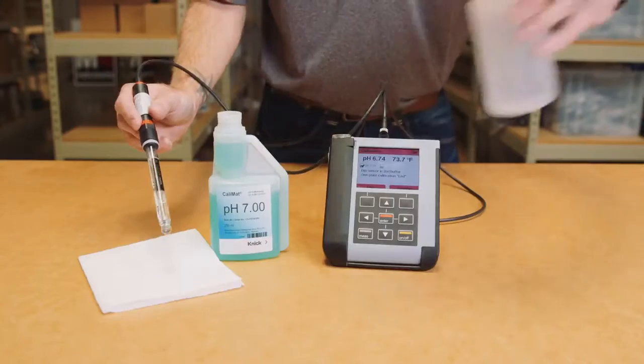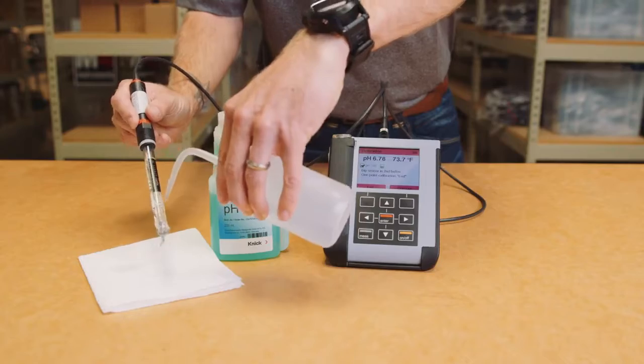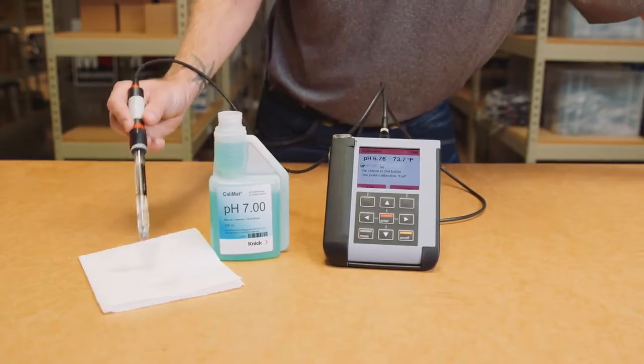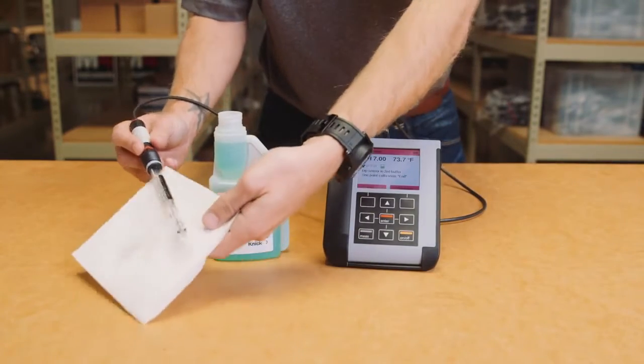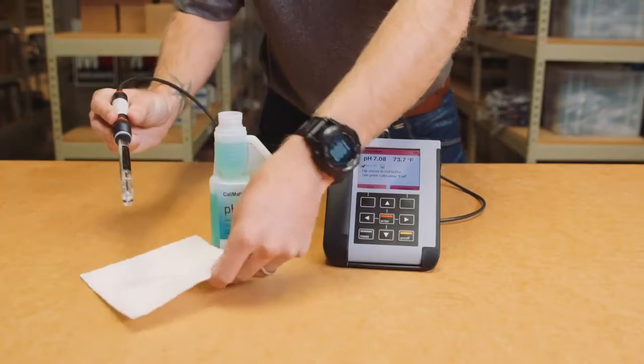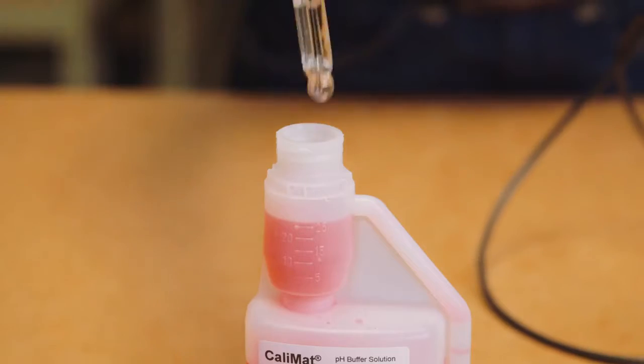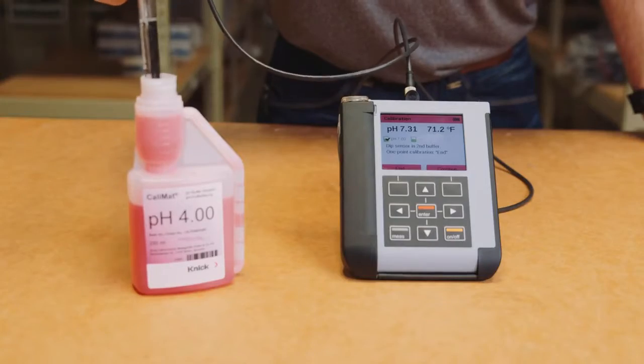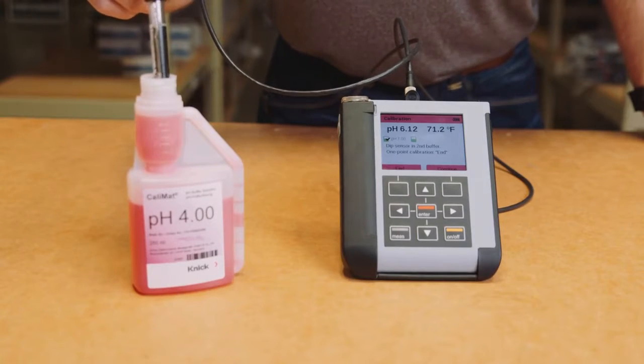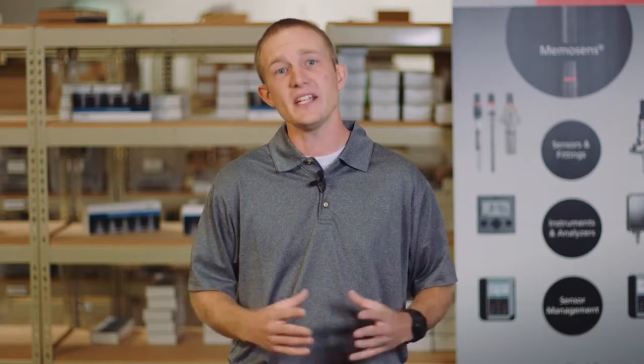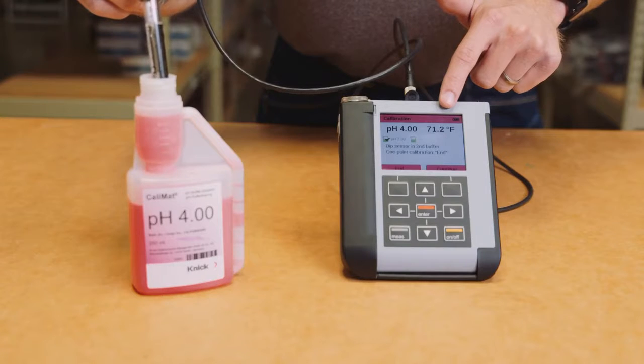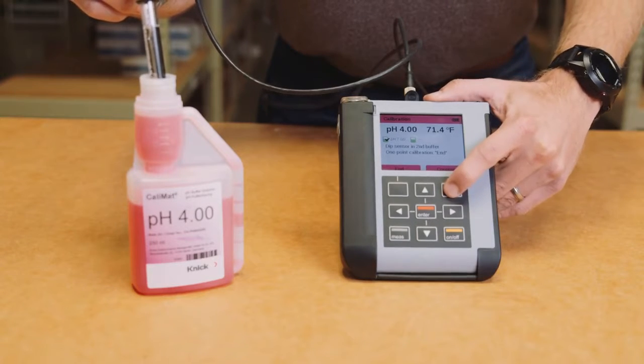You'll now want to rinse the sensor with a cleaning solution such as distilled water prior to putting it in the second buffer solution. Then dab it dry, being very careful not to rub the glass bulb. Now, repeat the process in the second buffer. Once again, stir lightly and make sure the junction is completely immersed. It's very important that the pH and temperature values stabilize before you press Continue. Once the values have stabilized, we can go ahead and press the Continue button on the Portavo.